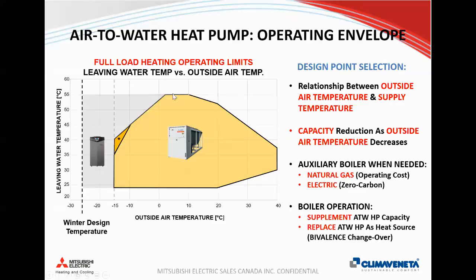So for example, if you had a 55-degree supply, the boiler could do half that load and the heat pump could do the other half of the load. But what's going to happen as it gets colder into the evening later on in that day, eventually for a 55-degree Celsius set point, eventually your heat pump, if the return water temperature is low enough, meaning you have a load, the heat pump can add heat to that, but it still has limitations due to the refrigerant to hit a maximum supply temperature. So for example, in the evening, if it's -10, the maximum leaving water temperature from the heat pump is 45 degrees.